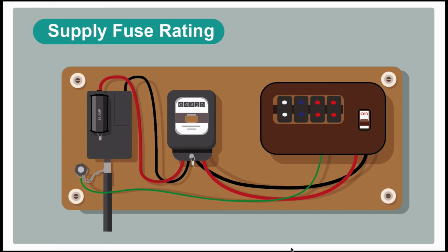When we're doing our initial checks on the incoming services, we need to consider the size of the supply fuse. Generally, if it's an older property, it's going to be 60 amps. That might need upgrading to a 100 amp supply if they're going to be using things that need more current, the vehicle charging and such. So that's the job for the DNO. You're going to have to get in touch with them. You'll have to fill in a form, tell them why you want your service altered. You can do this all online. You fill the form in and they'll come around and have a look and see what they need to do.